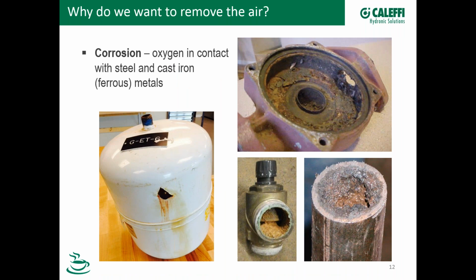Another big issue, and this is a significant problem, is corrosion. If you have oxygen in contact with steel and cast iron, this is the result. Corrosion causes a lot of damage. You can see here this pump volute, and you can see the corrosion inside of this mixing valve down below. Obviously that valve isn't going to work very well. And you can see corrosion in the pipe. And then on this expansion tank, because air is about 23% oxygen, that's what drives this corrosion. And chronic air problems can cause serious damage and eventual failure of components like this.